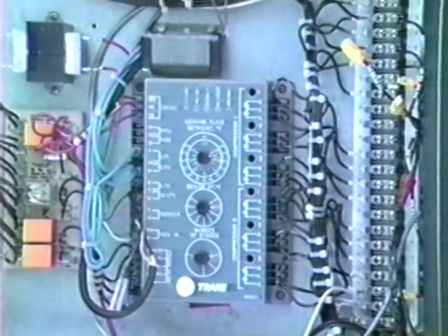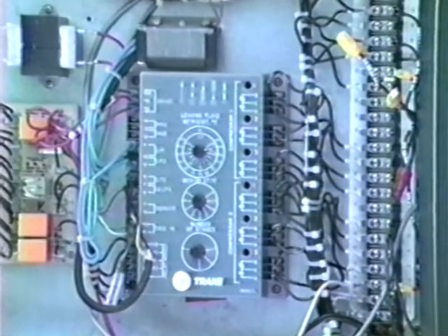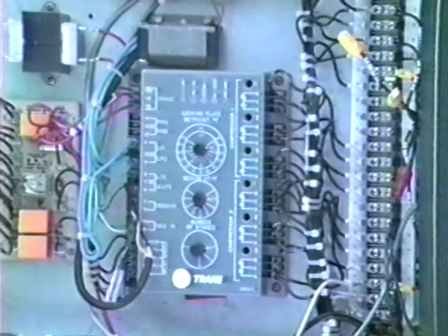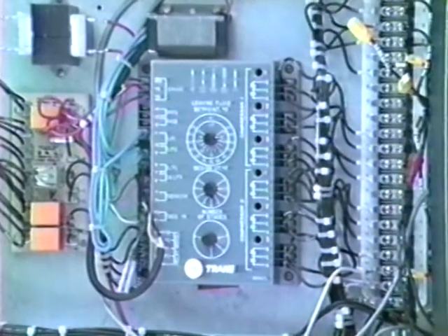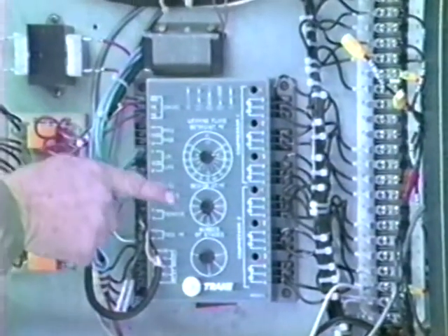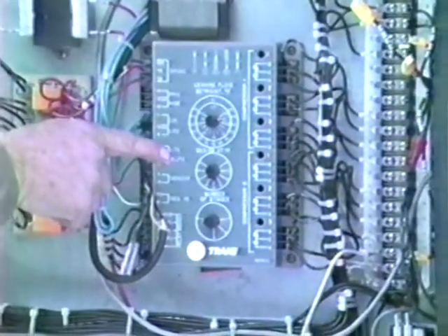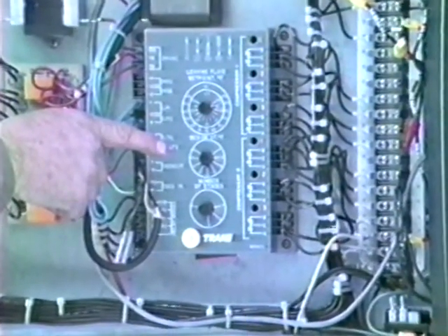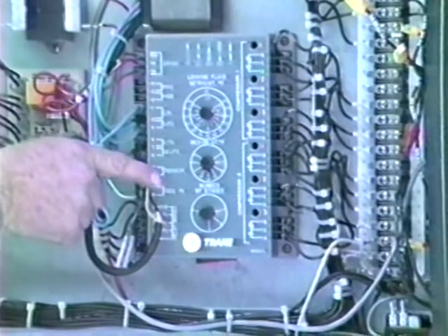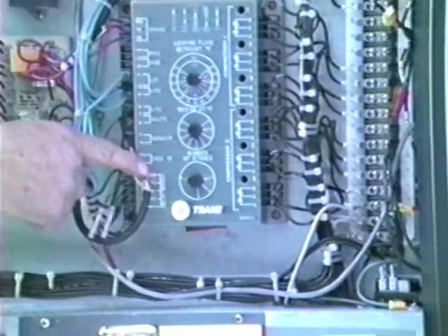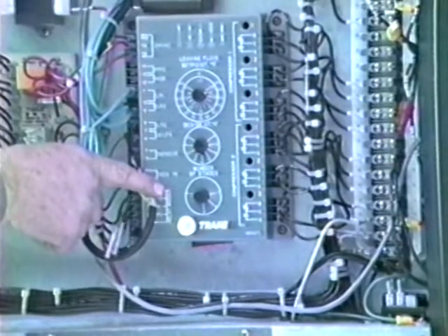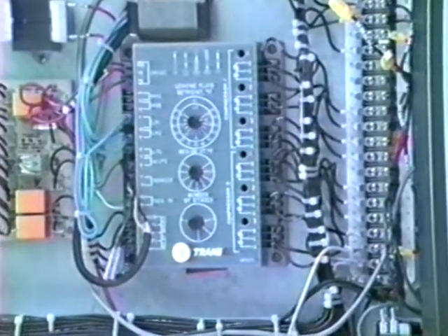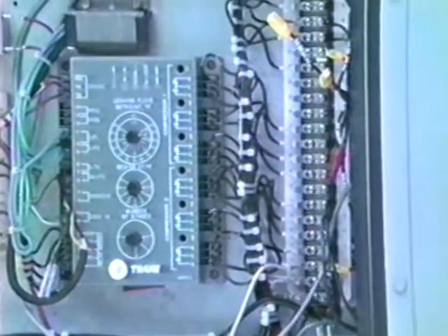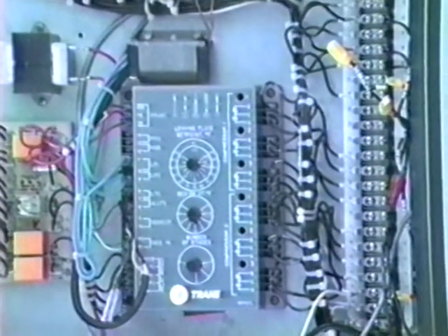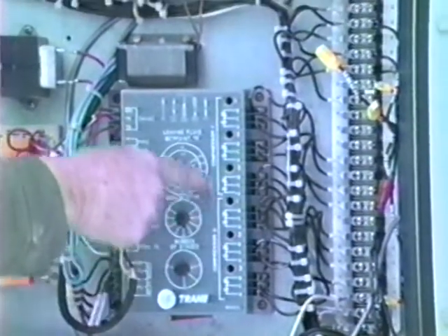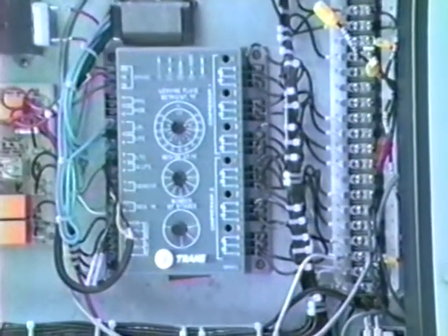We're now looking at the leaving fluid temperature set point dial. There's 3 dials there. The top one, Roy, indicate the top is the leaving fluid temperature set point. The next dial there is the design temperature difference. The bottom one, what is the bottom one, Roy? I can't see it. Number of stages. Yeah, right. That's the number of stages that the chiller will perform. The little dots, vertical row of dots to the right of that, are the compressor stages LED lights.